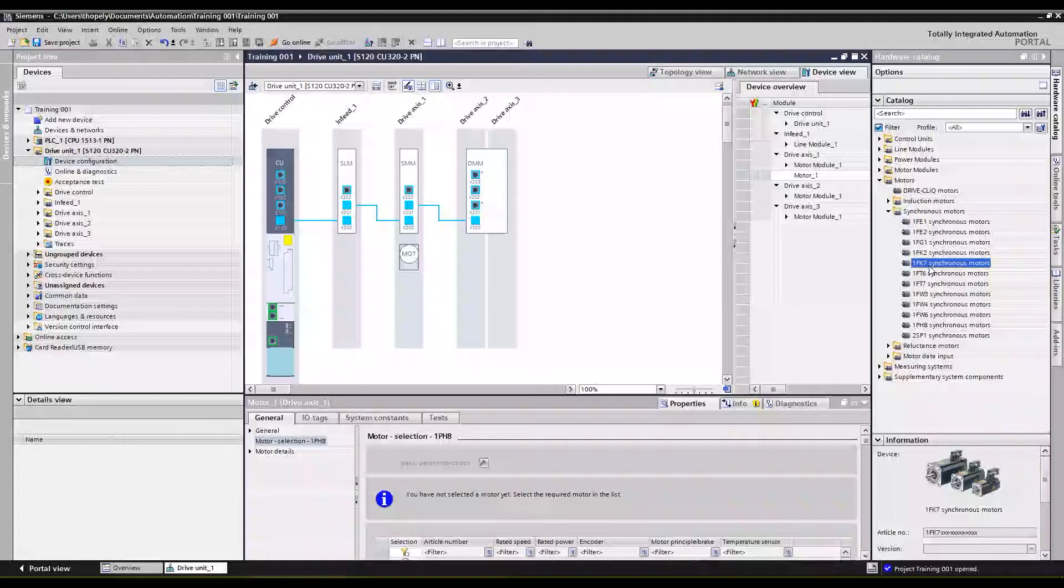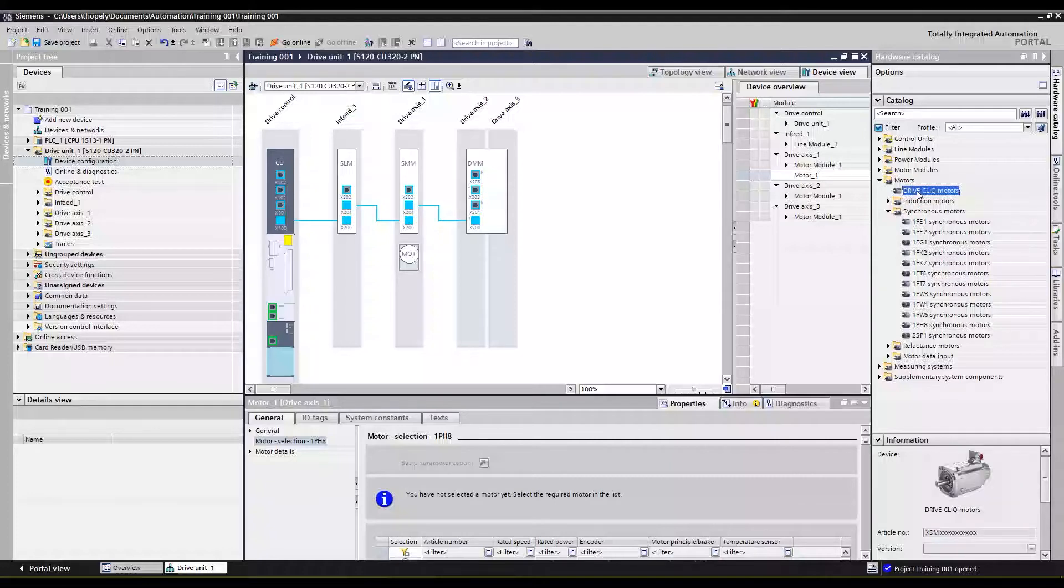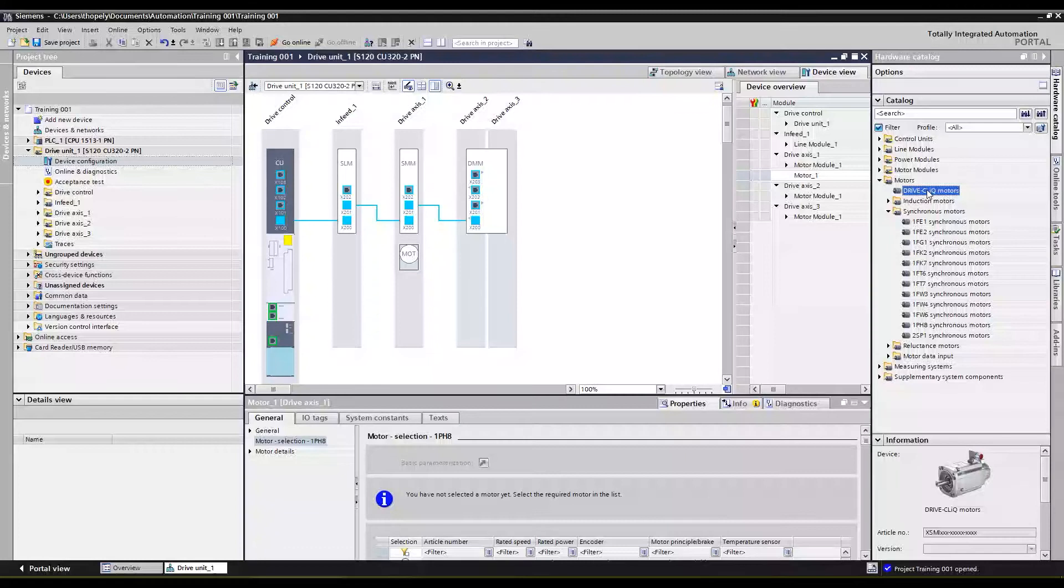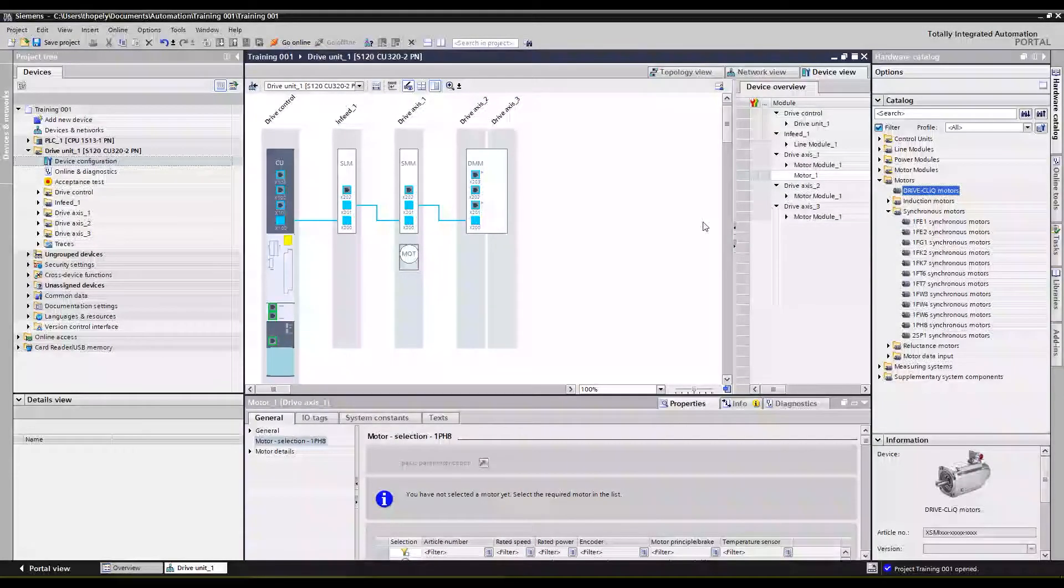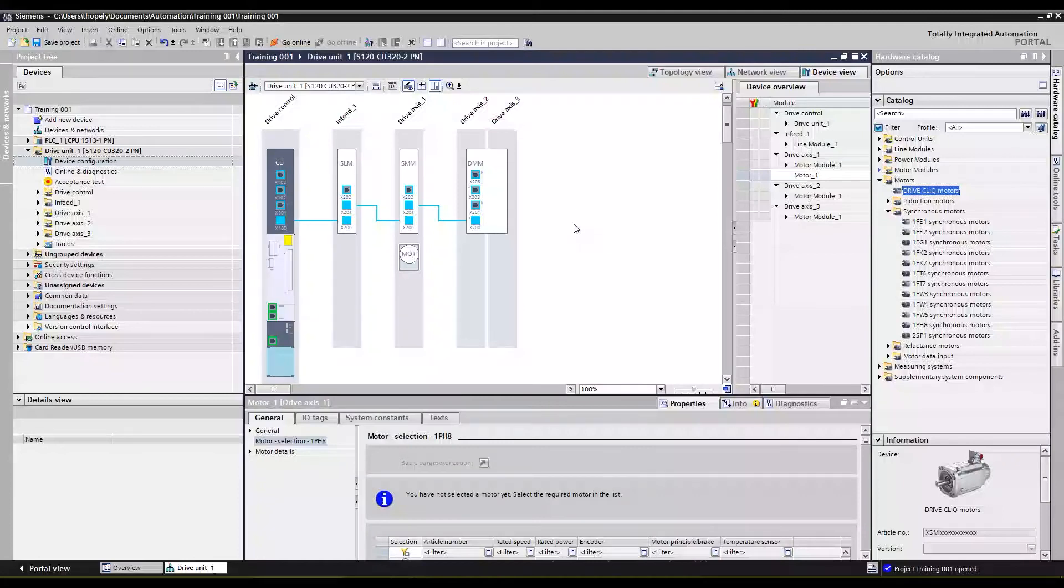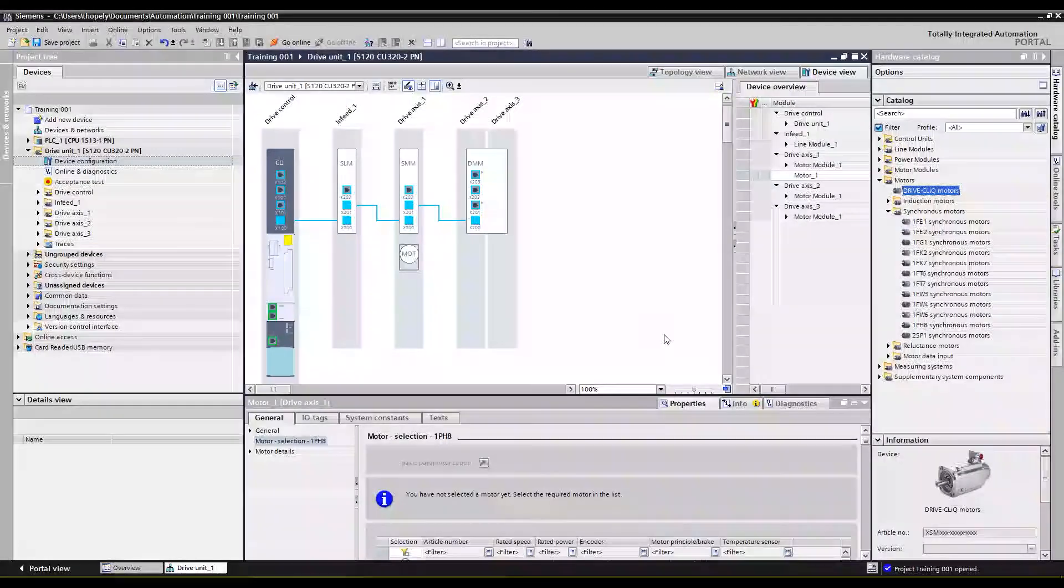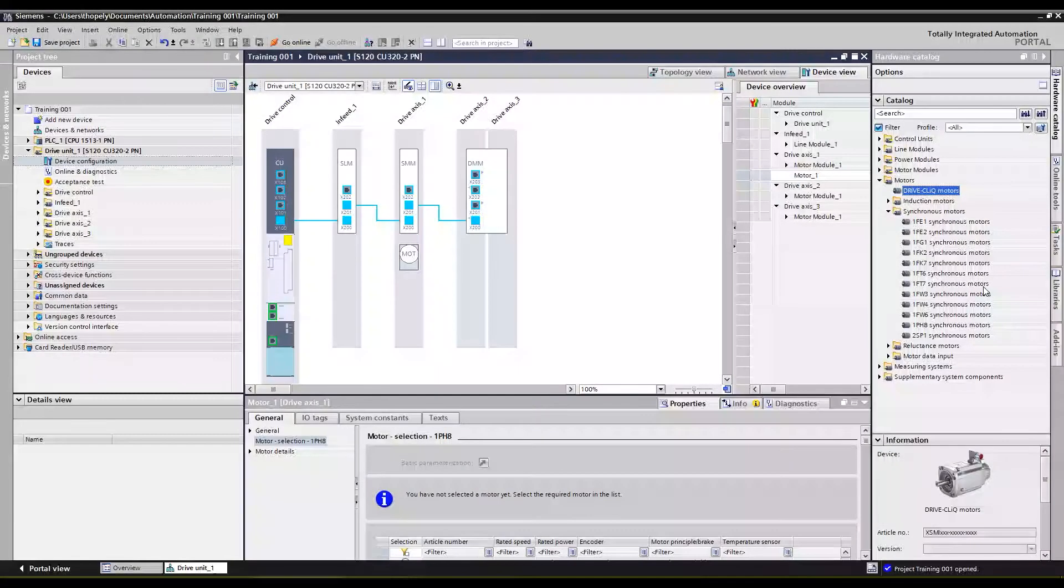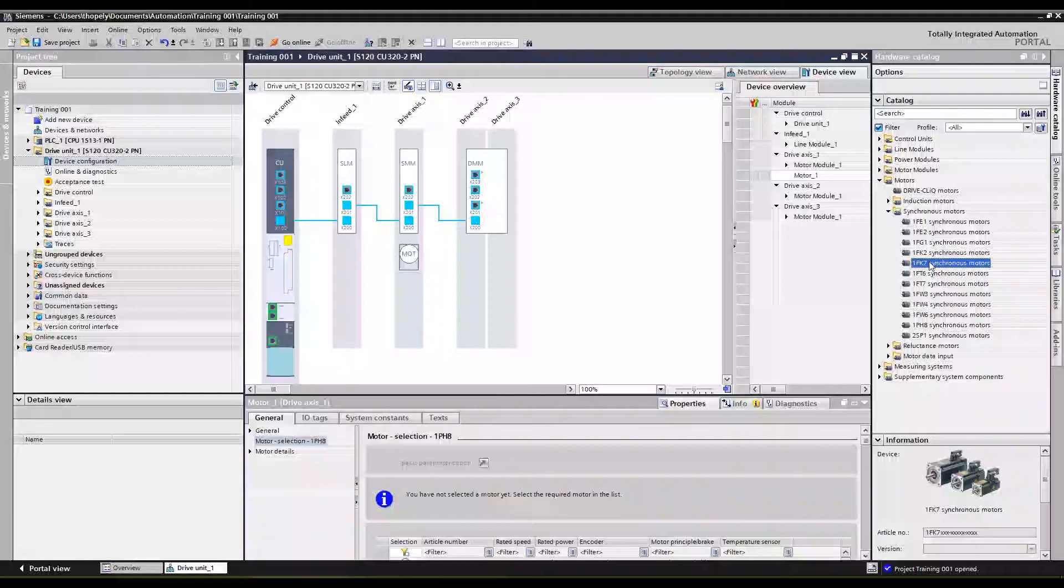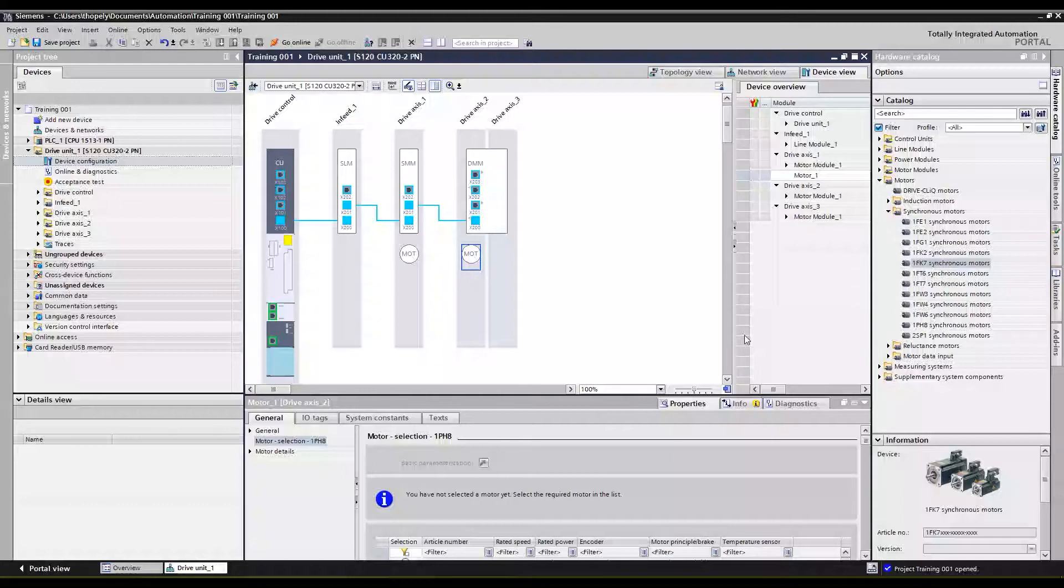But then for the double motor module we're also going to go with a Siemens 1FK7 servo motor. And I just want to point out that you see up here we do have the DRIVE-CLiQ motor option available. If you're going to connect up to your hardware, you can just drag and drop this DRIVE-CLiQ motor onto your motor modules, and once you connect up to the hardware the CU is going to reach out and read everything over DRIVE-CLiQ and find all the nameplate data of that motor, and you don't have to go through and pick the details out. We're not going to do that today because I don't have hardware to connect to, so I'm going to manually pick a 1FK7 motor even though it will be a DRIVE-CLiQ 1FK7 motor. You can do it either way.